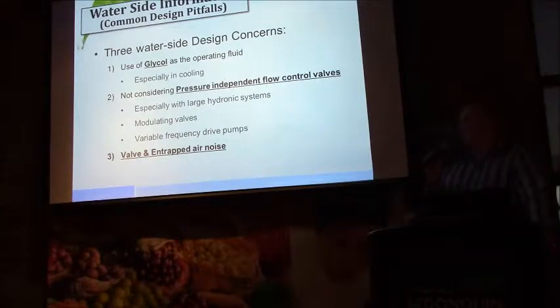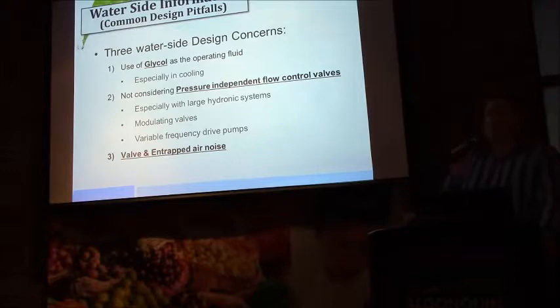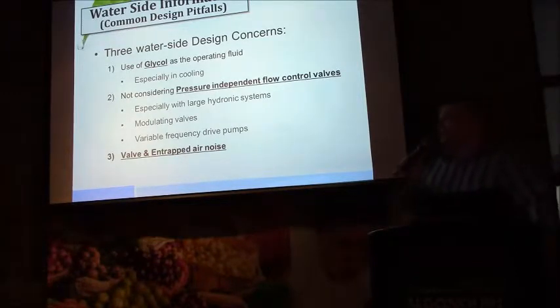It's low-grade energy, granted, and if the pumping calculations don't make sense for that to be effective, it may not be an option. But generally, decoupling the building loop from that secondary cooling opportunity on the water side is a good strategy. Glycol is expensive, for starters, and glycol through the beams really impacts the performance of the coil, particularly at low temperature. In heating, it's not an issue, but due to both the cost of coil, the cost of glycol, and the impact to its performance of the active beam, glycol is generally not recommended to be circulated to the beams themselves. You'll need that in the coil that creates your free chilled water, or your waterside free cooling, sorry. But as a general rule of thumb, glycol through the beams is a bad idea.